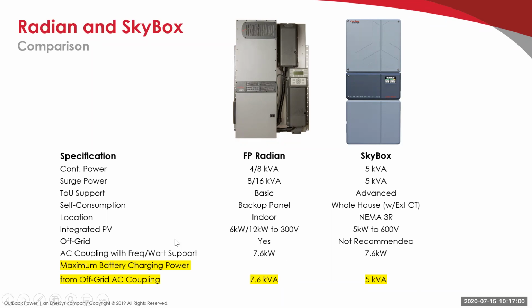AC coupling, and again, these last two I will let Mark talk about in his presentation, which I believe starts right after this slide. They both can support a 7.6 kilowatt grid-tied inverter, even though this one is only 5 kilowatts, which does limit the power. Now, the caveat with the Skybox is it needs to be a 7.6 kilowatt inverter that is UL 1741 SA compliant. If it's an older inverter, then the Skybox can only support a 5 kVA grid-tied inverter. So again, Mark will touch a little more on that.